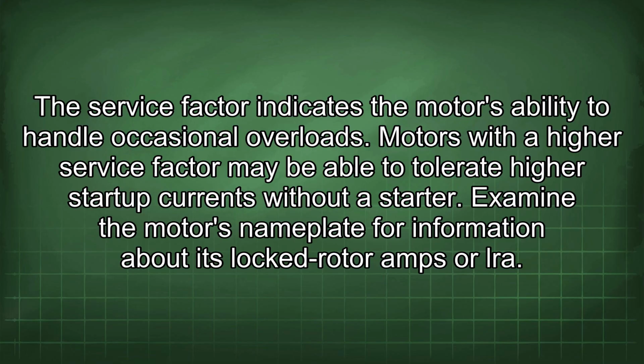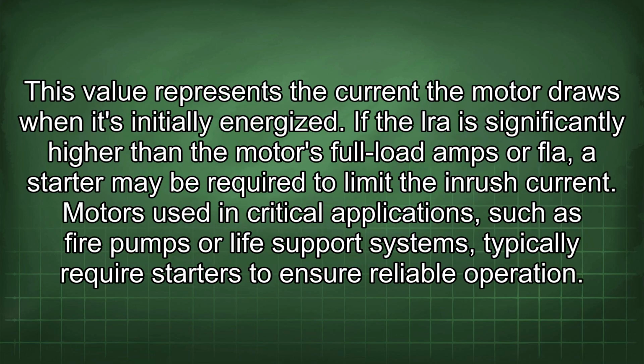Examine a motor's nameplate for information about its locked rotor amps or LRA. This value represents the current the motor draws when it's initially energized. If the LRA is significantly higher than the motor's full load amps or FLA, a starter may be required to limit the inrush current.